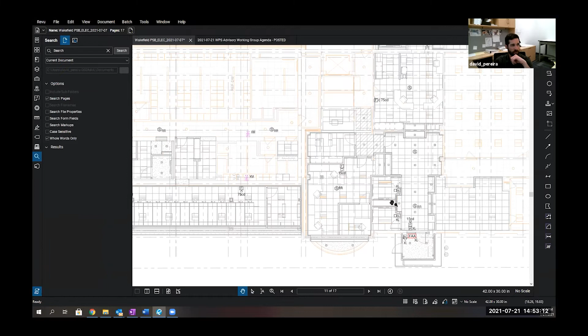So can we list 3 manufacturers, or do we not list? We basically list the fire alarm control panel that we're extending, and then we spec the devices, the properties of the devices, the Candela ratings, the materials, and their mechanical and electrical specifications. We also note that they need to be UL listed with the existing panel, and then they'll provide the appropriate device.